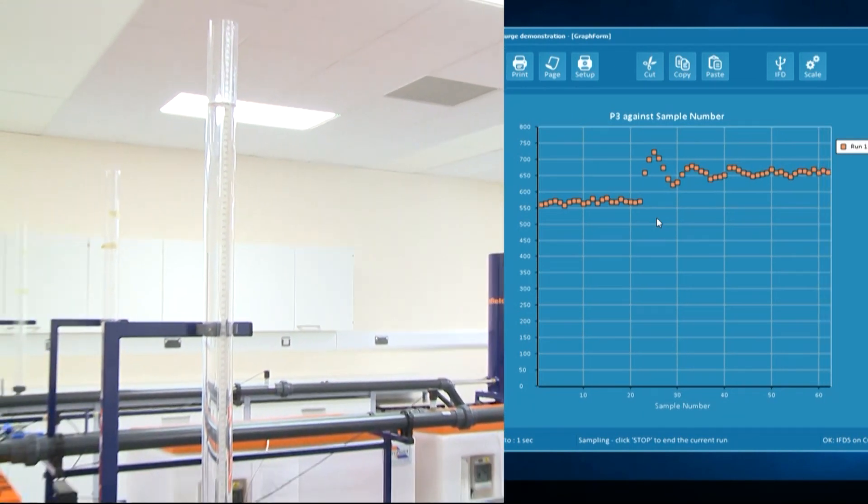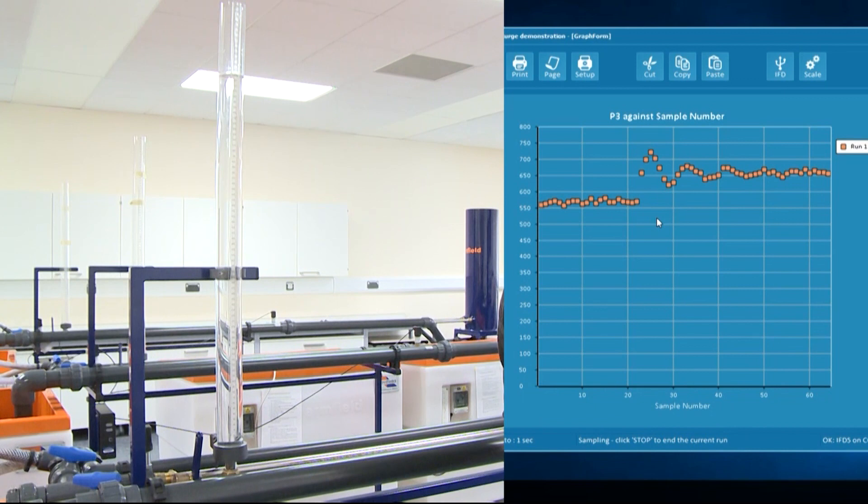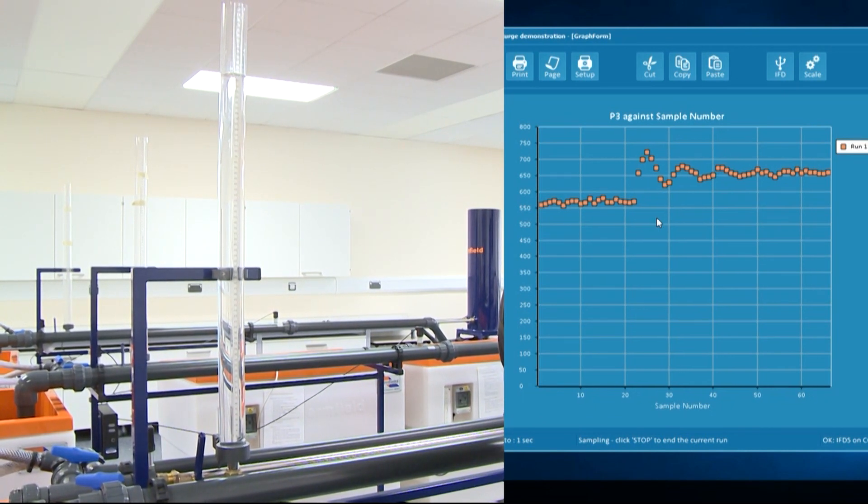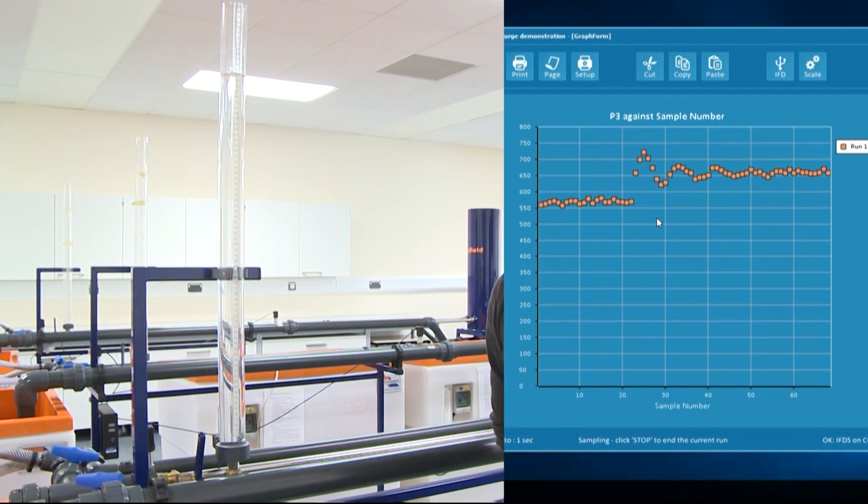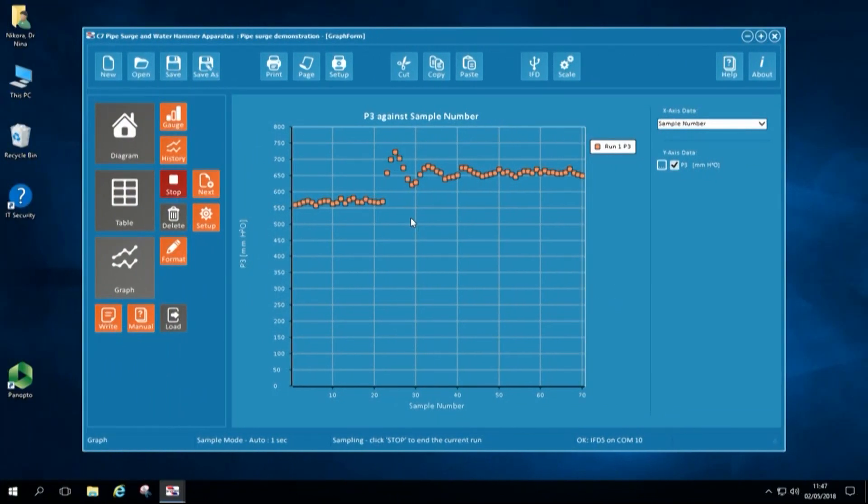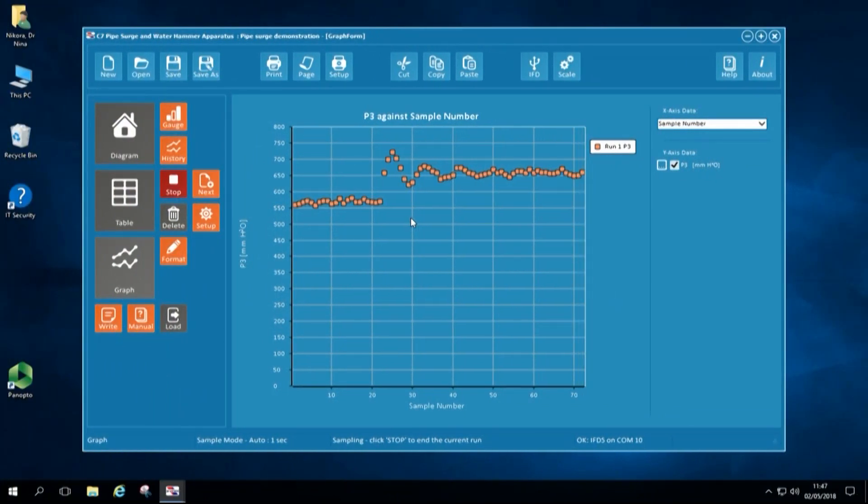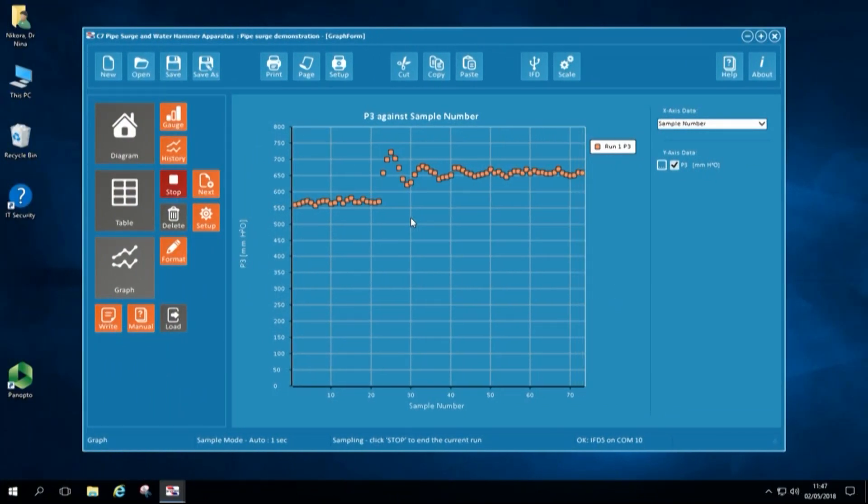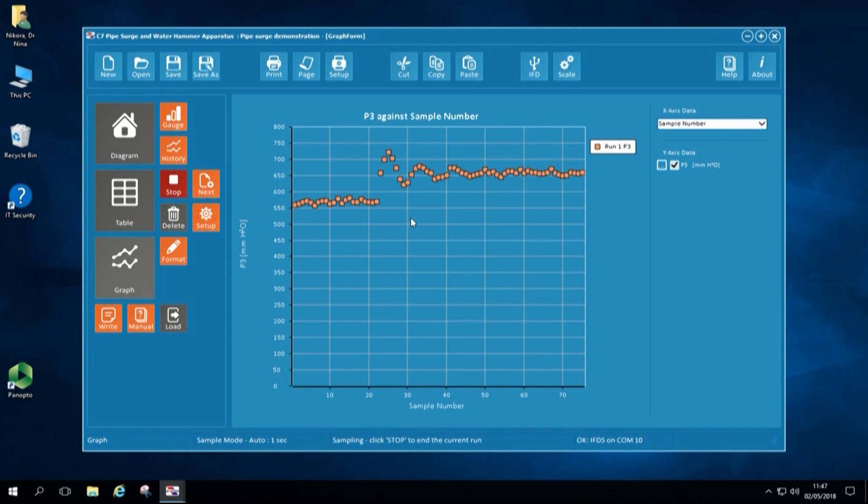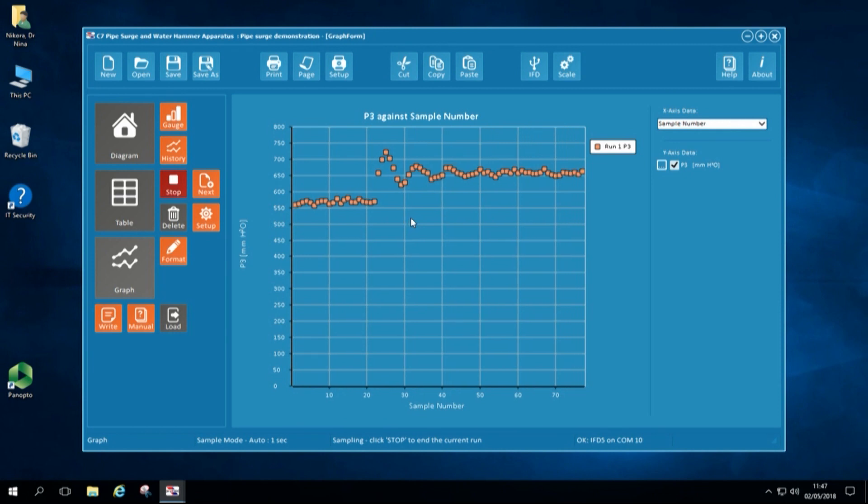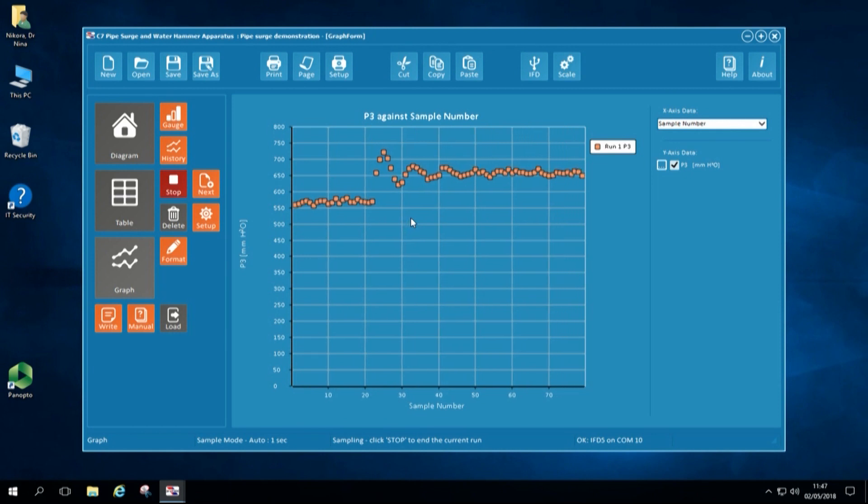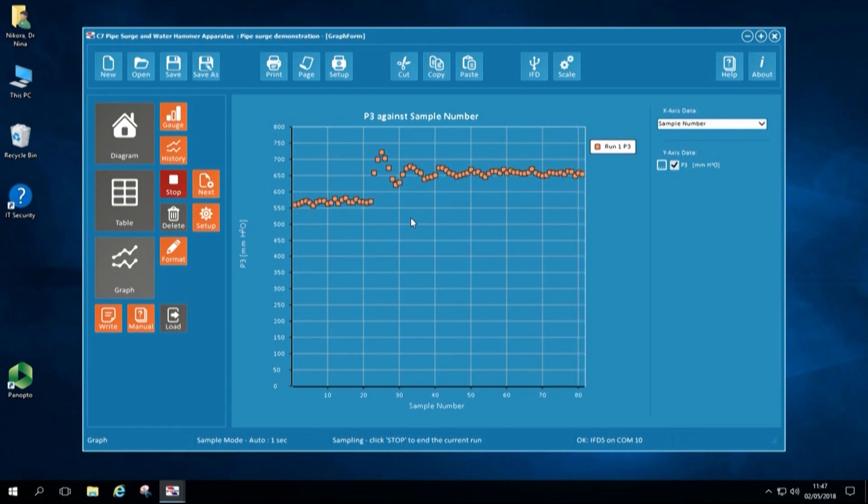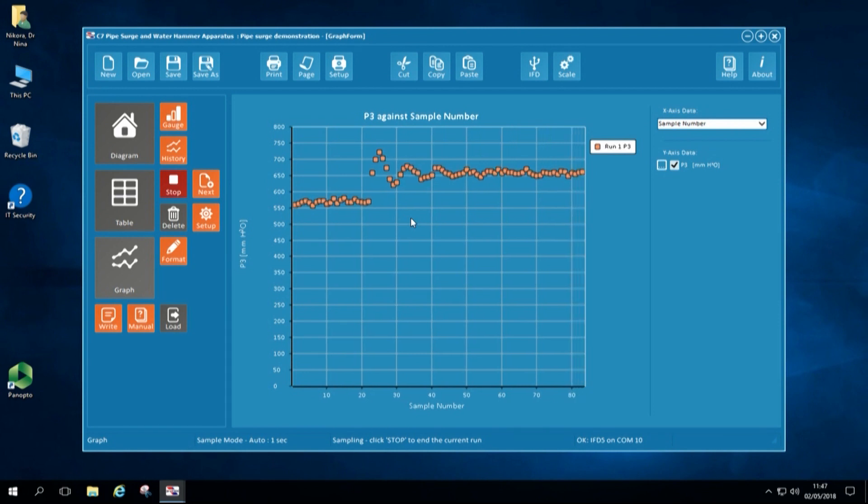We can see that the water level is almost stable in the surge tower and this is confirmed by recorded water level on the graph, which is static level in the surge tower. We will record this for a few more minutes before we open the valve again.